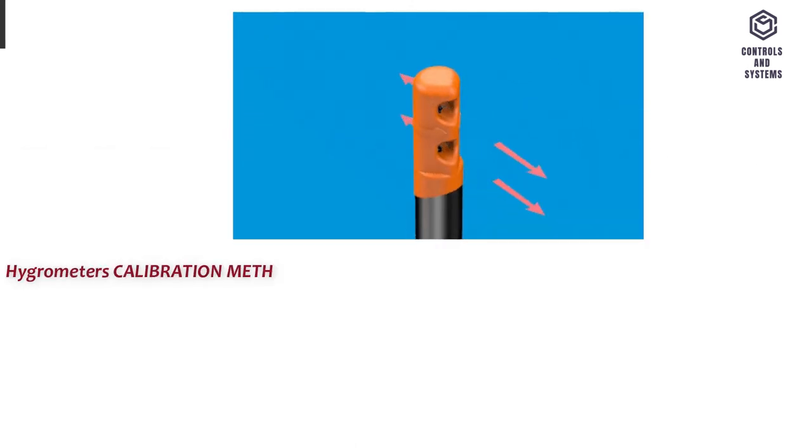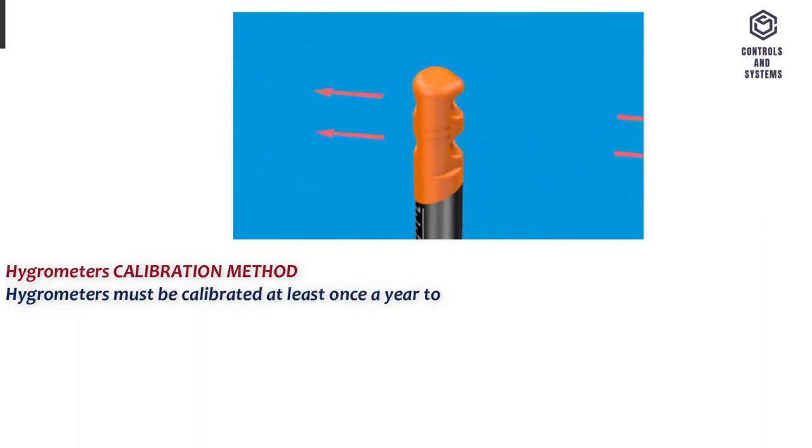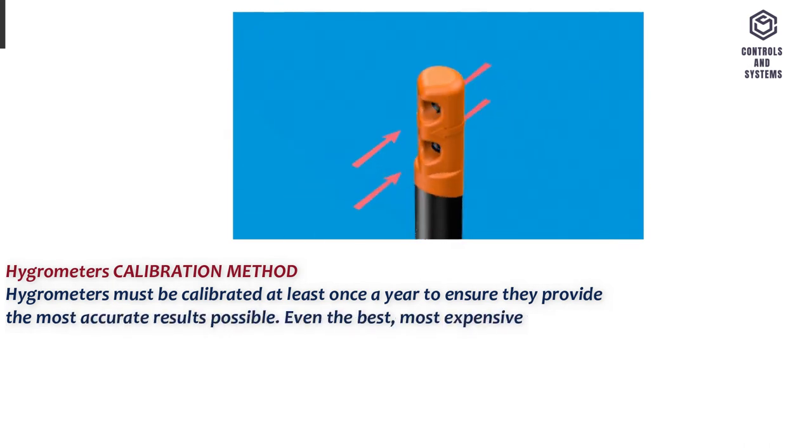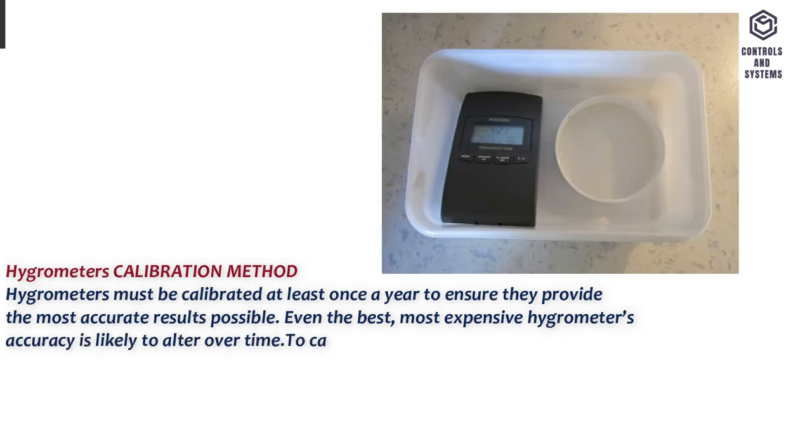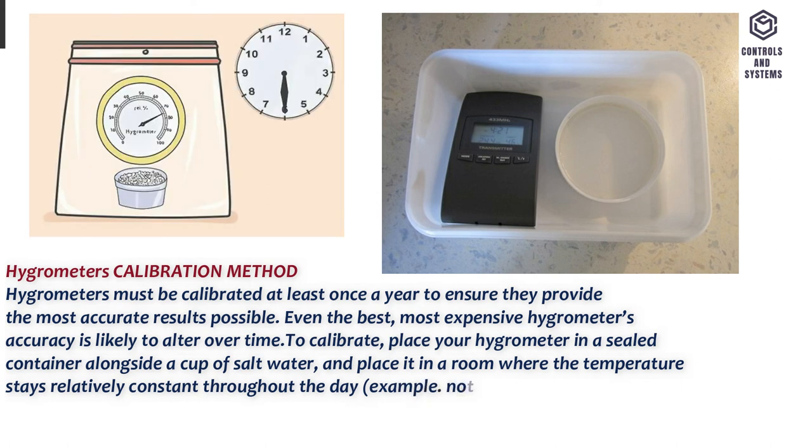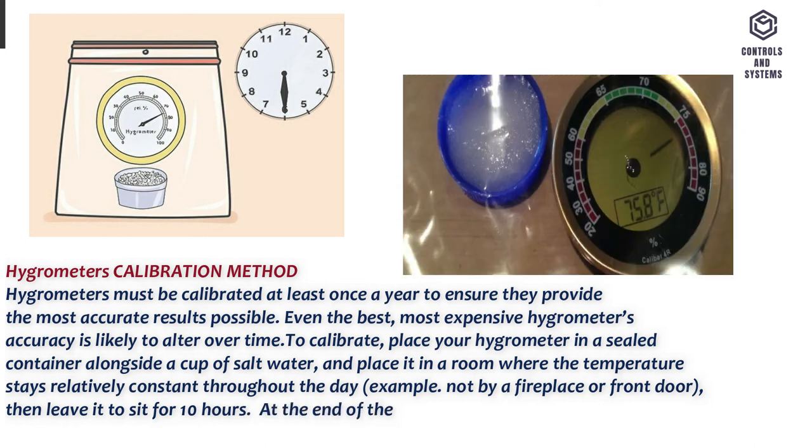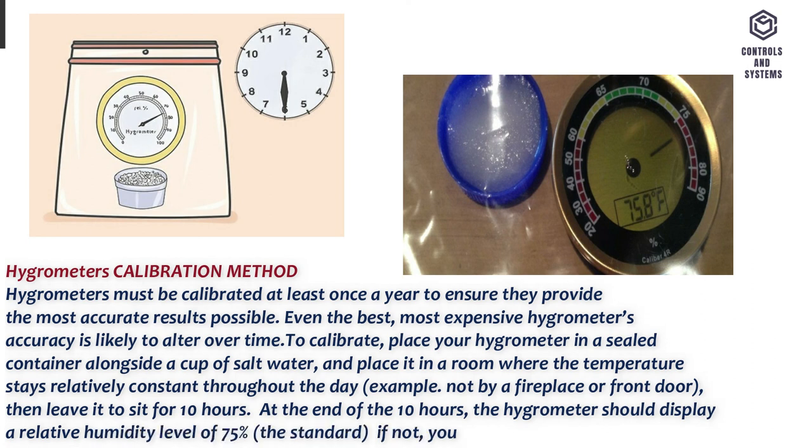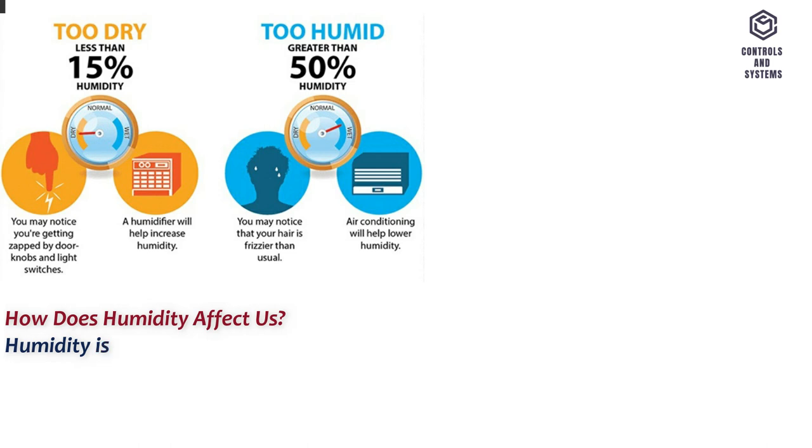Hygrometers calibration method. Hygrometers must be calibrated at least once a year to ensure they provide the most accurate results possible. Even the best, most expensive hygrometers accuracy is likely to alter over time. To calibrate, place your hygrometer in a sealed container alongside a cup of salt water, and place it in a room where the temperature stays relatively constant throughout the day, for example not by a fireplace or front door, then leave it to sit for 10 hours. At the end of the 10 hours, the hygrometer should display a relative humidity level of 75%, the standard. If not, you need to adjust the display.